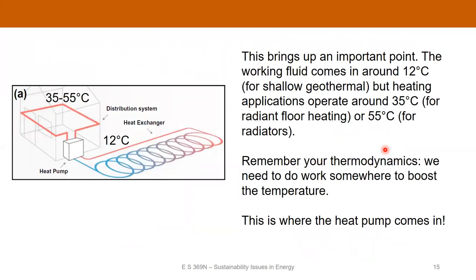This brings up an important point. In winter, a shallow geothermal system might deliver working fluid at around 12°C, but you need the water circulating through your baseboard radiators or radiant floor heating to be somewhere between 35 and 55°C. That's obviously much hotter than your working fluid. So we need to do work to the fluid to boost the temperature — and that's where heat pumps come in.